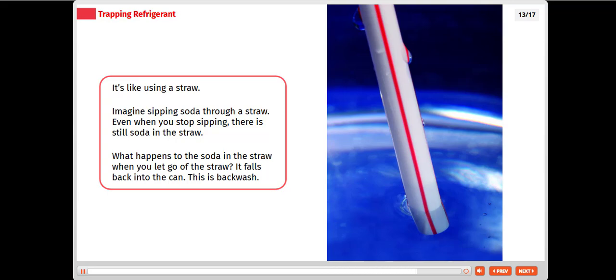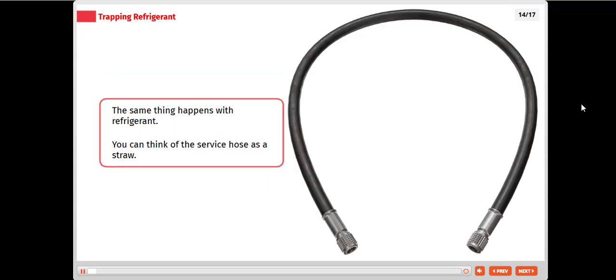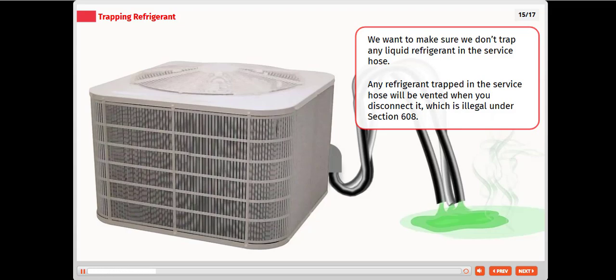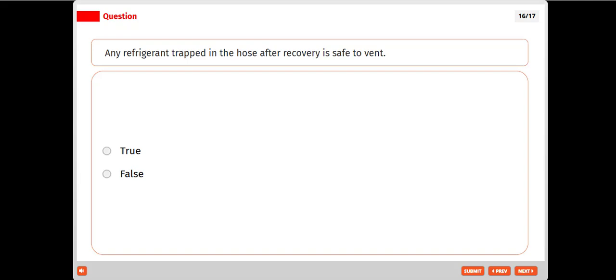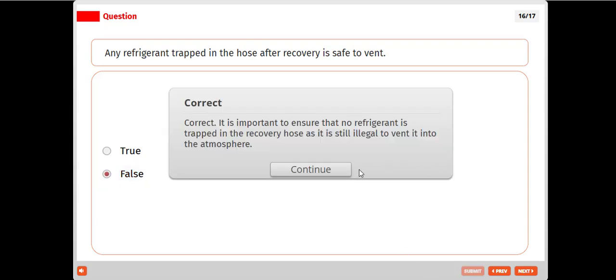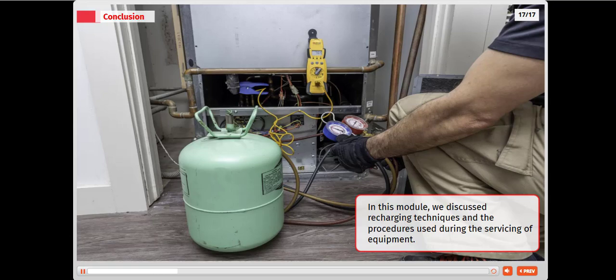The same thing happens with refrigerant. You can think of the service hose as a straw. We want to make sure we don't trap any liquid refrigerant in the service hose. Any refrigerant trapped in the service hose will be vented when you disconnect it, which is illegal under Section 608. Any refrigerant trapped in the hose after recovery is safe to vent? No. In this module, we discuss recharging techniques and the procedures used during the servicing of equipment.